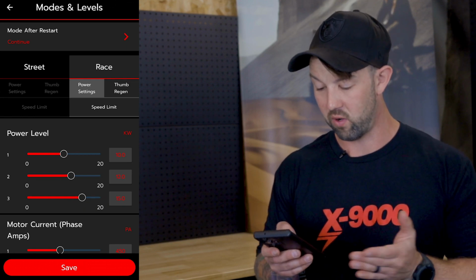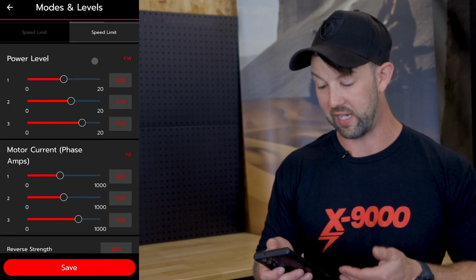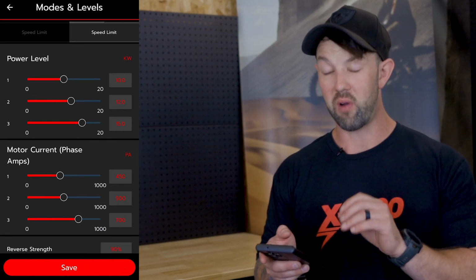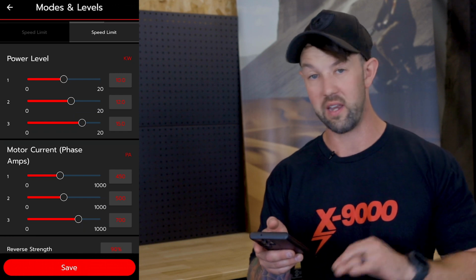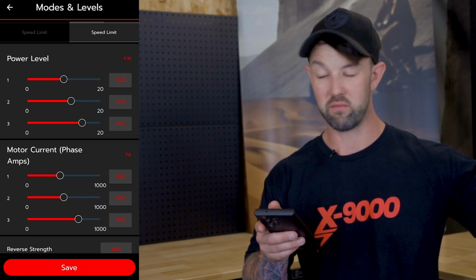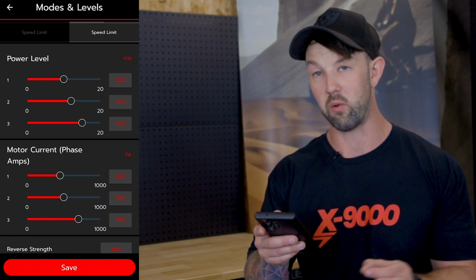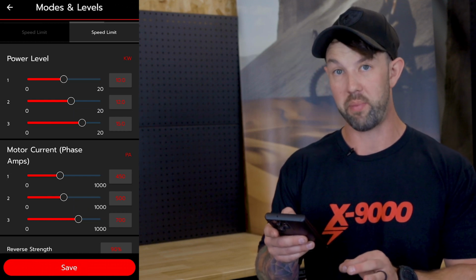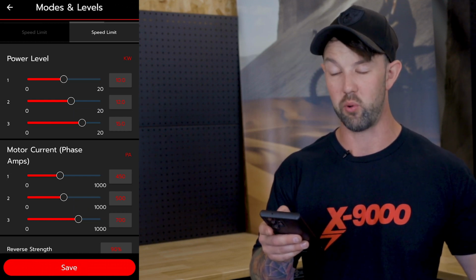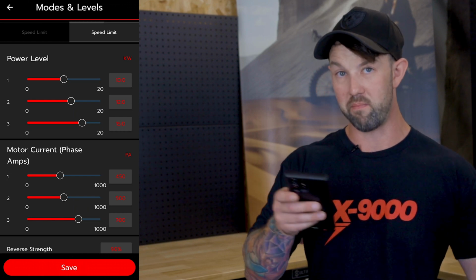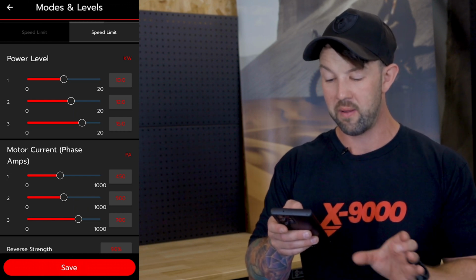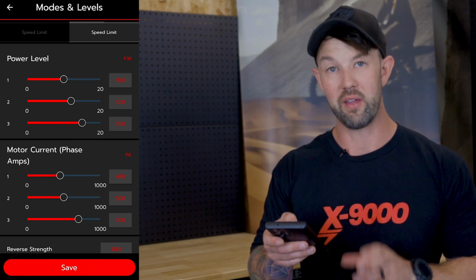So in street, if we look through our power modes, this is basically the peak level. This is controlled by the current you set previously. So if you set 100 amp DC at 20S and then set 20 kilowatts here, you're never going to hit 20 kilowatt peak because you'll be limited by the DC amps you put in. So remember, whatever you match as your peak current limit is going to be the peak power limit you put in here.